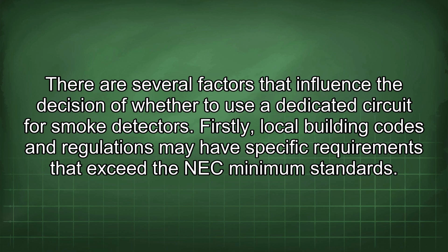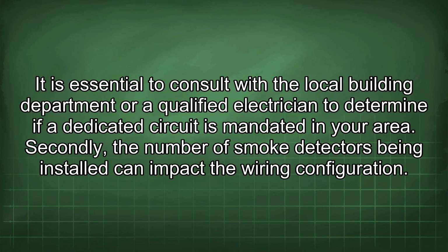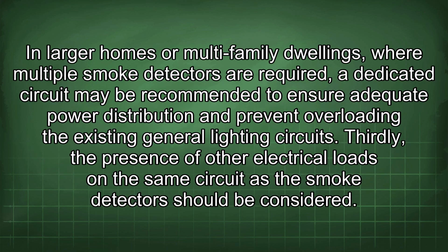There are several factors that influence the decision of whether to use a dedicated circuit for smoke detectors. Firstly, local building codes and regulations may have specific requirements that exceed the NEC minimum standards. It is essential to consult with the local building department or a qualified electrician to determine if a dedicated circuit is mandated in your area. Secondly, the number of smoke detectors being installed can impact the wiring configuration. In larger homes or multi-family dwellings, where multiple smoke detectors are required, a dedicated circuit may be recommended to ensure adequate power distribution and prevent overloading the existing general lighting circuits.